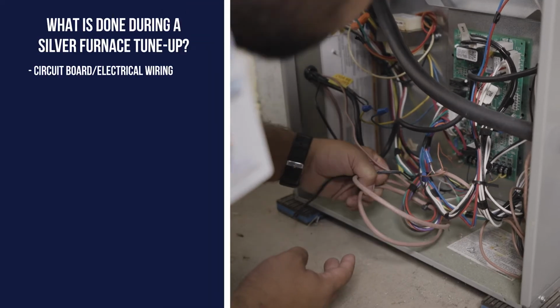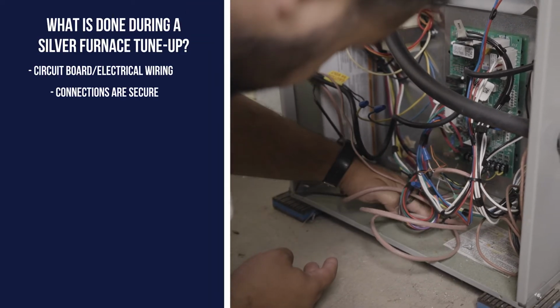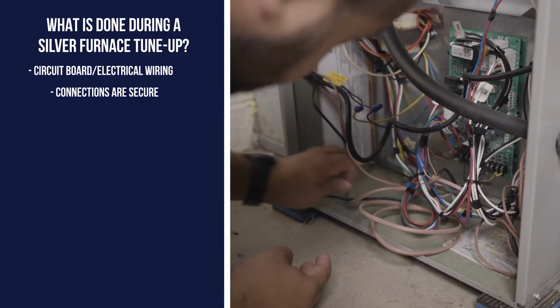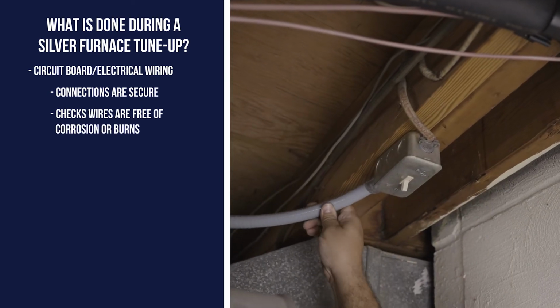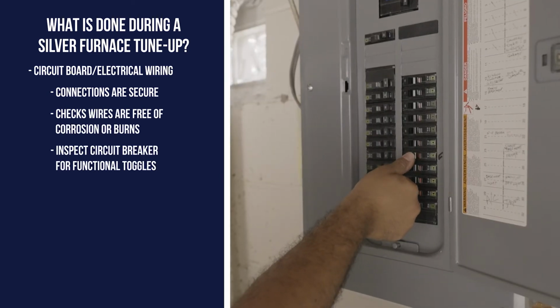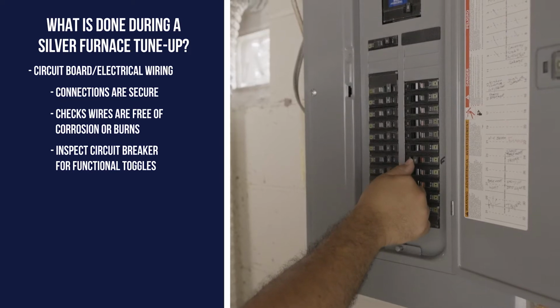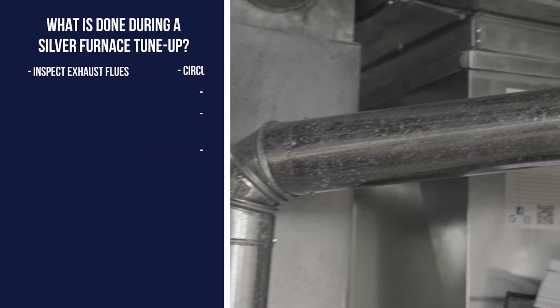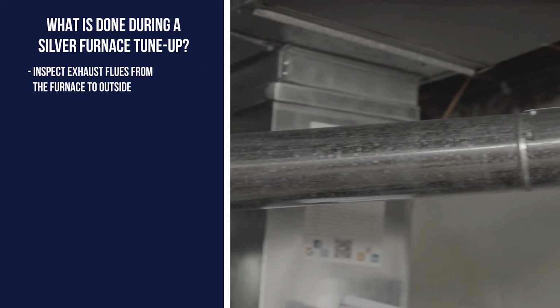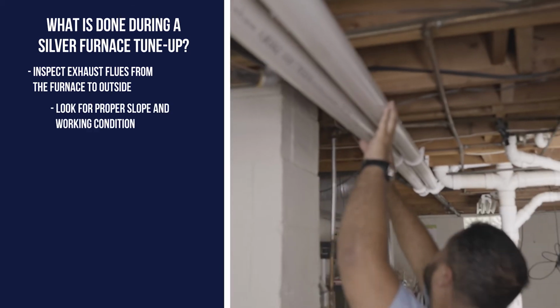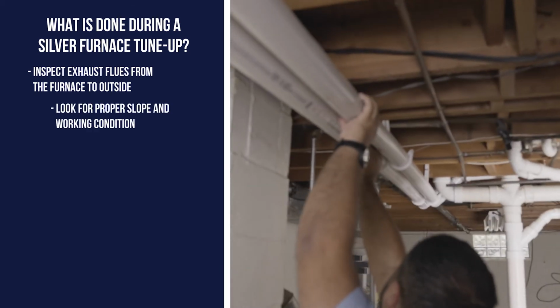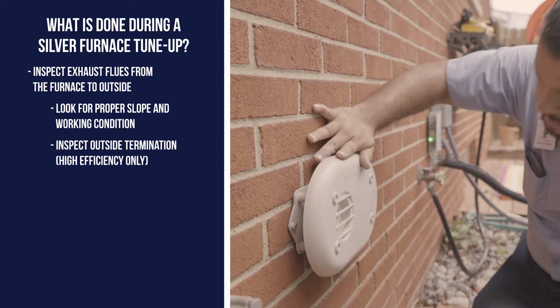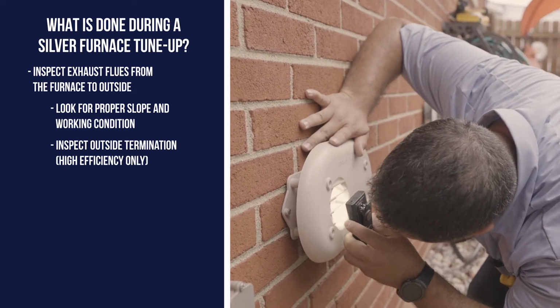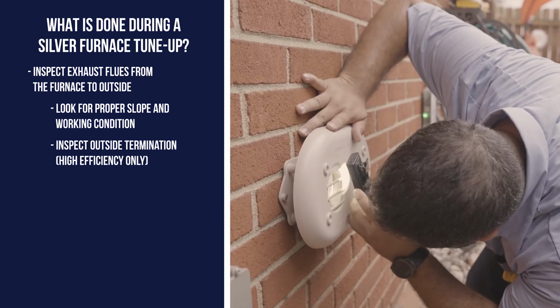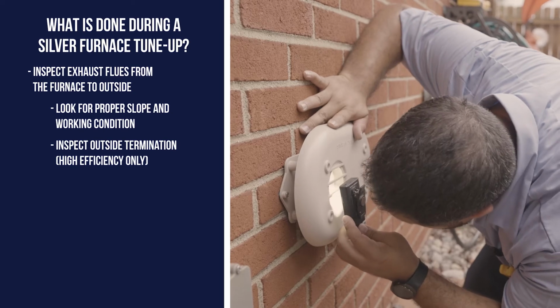Next up is the furnace's circuit board. We make sure all wiring connections into and out of the furnace are secure and free of any corrosion or burns. We'll also inspect the breaker to make sure the switches are functional. We then inspect the exhaust flues from the furnace to the outside. We make sure they have proper slope and that they are in good working order. For high efficiency furnaces, we inspect the outside termination to ensure that it's free of obstructions and installed correctly.